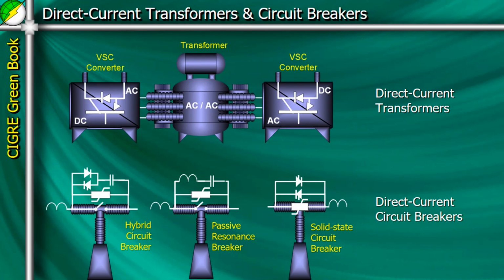The three main concepts being researched today for implementing a direct current circuit breaker are: a hybrid circuit breaker, with a mechanical switch together with an active circuit that can temporarily create, via an external signal, an oscillating circuit in parallel with the mechanical switch to interrupt the current; a passive resonance breaker, where a parallel network with the mechanical switch can oscillate during the opening of the switch to create conditions for interrupting the current; and a more advanced concept that gets rid of the mechanical switch entirely and uses a solid state circuit breaker. These three concepts are being developed.